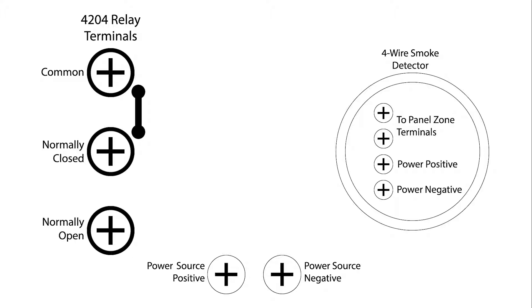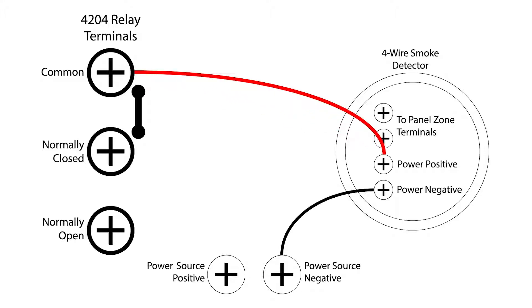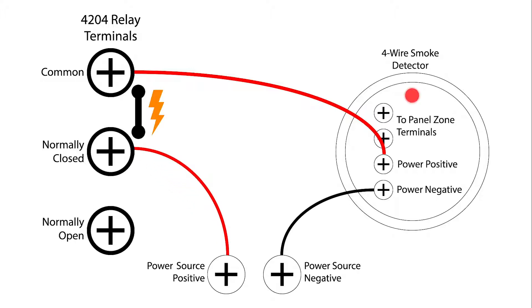You will have two terminals on the smoke detector that go to a zone on the panel. The other two terminals are for power. Connect the negative from your smoke to the negative of your power source. Next, connect the positive of your smoke to the common terminal of the relay. Lastly, connect the positive of your power source to the normally closed of your relay. The circuit will be complete and your smoke will have power.